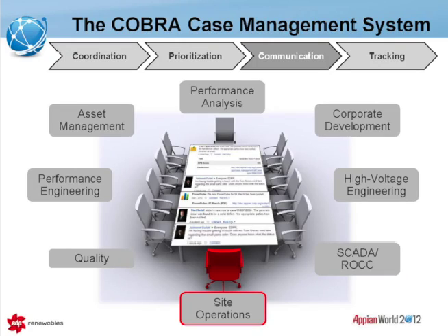But in the back end, this has been automatically calculated to reduce the bias from the users. We don't want the users to specify how urgent the case is. We want our databases and our system to figure out how important this case is for our company by taking into account power prices, NCFs, and everything, NCFs being our capacity factor, how much of our turbines are supposed to produce, are actually producing, as opposed to how much they could produce. So everything plays in, all the performance metrics play in, and we have an RPN score. The next big thing is communication.